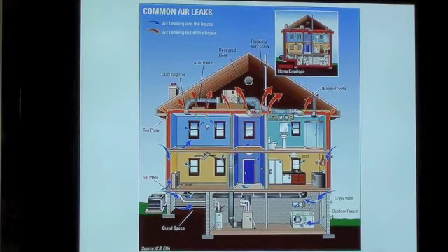So what do you do? The thing that our company offers is an energy evaluation. We come into the house and we document all the parameters of the house. We measure up the walls, we measure up the attic and the windows and doors, and we check how much insulation is in each of those components. We do an air tightness test of the house to find out how leaky it is. We document and verify the kind of mechanical equipment in the house: the ventilation system, does it have heat recovery? The efficiency of the water heater and of the furnace. And all that goes into a software program that the federal government has developed, and that's the basis of the EnerGuide for Houses program that's in place here in Saskatchewan for retrofitting an existing house.